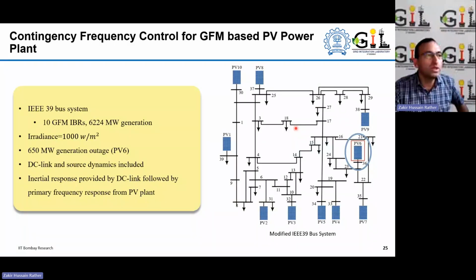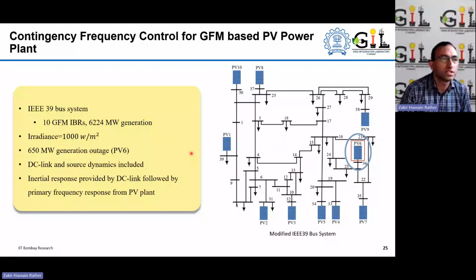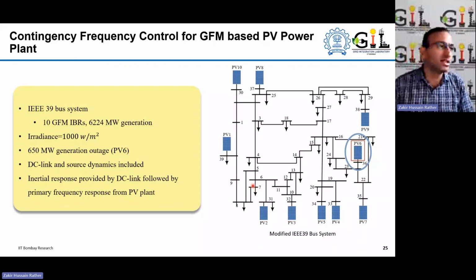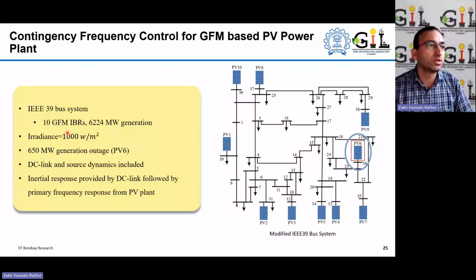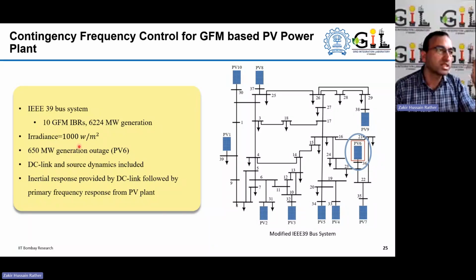Similarly, we looked at another aspect at IIT Bombay in terms of the system level studies. Here, what we have done is we considered a system which is technically 100% IBR based. This is the modified 39 bus test system, where we have 10 grid forming generators, total 6,220 megawatt generation. It is roughly 6 gigawatt peak load. And we have a constant irradiance of 1,000 watt per meter square considered for this. And we simulated a 650 megawatt generation outage in this system. That is PV power plant 6, which is connected to bus 36.